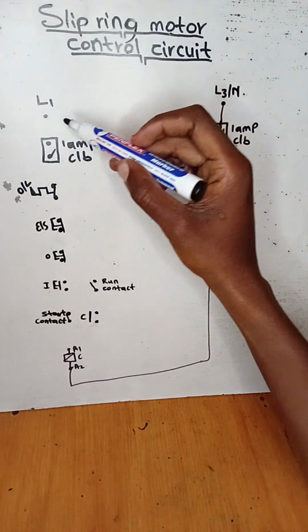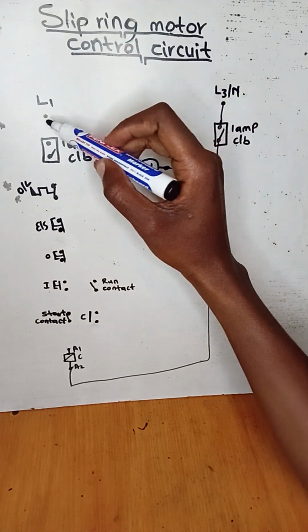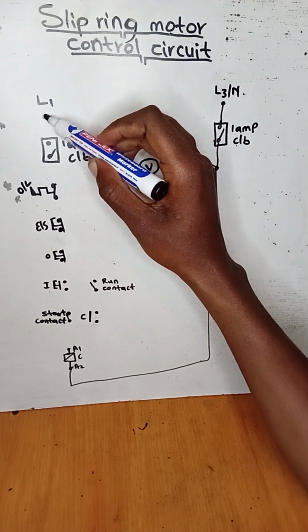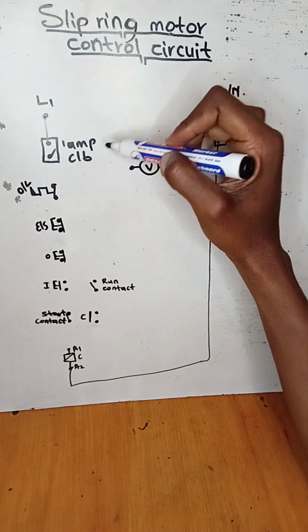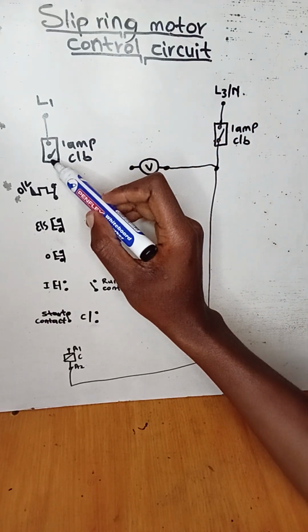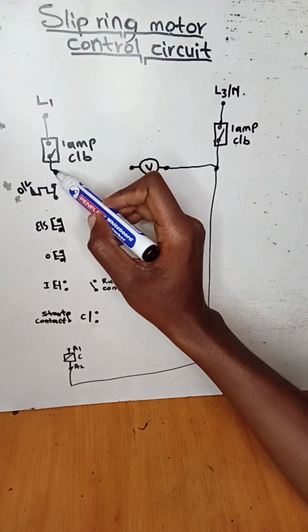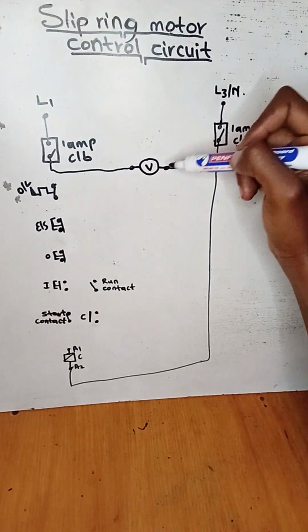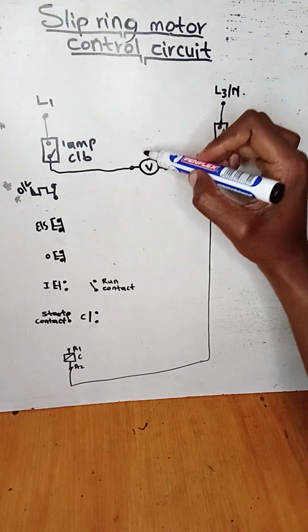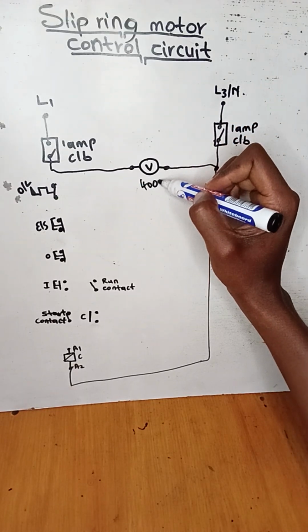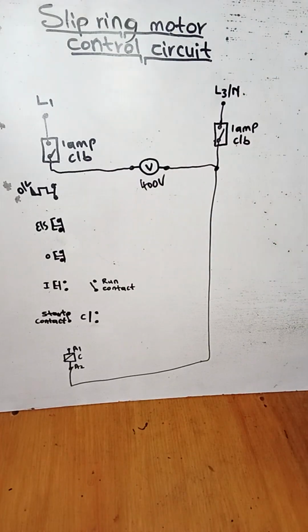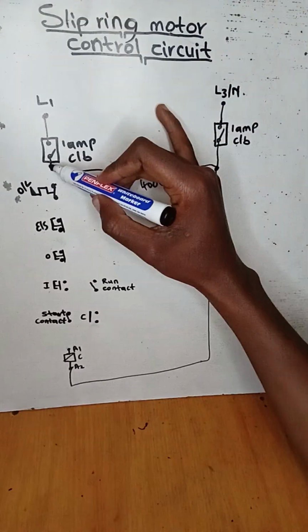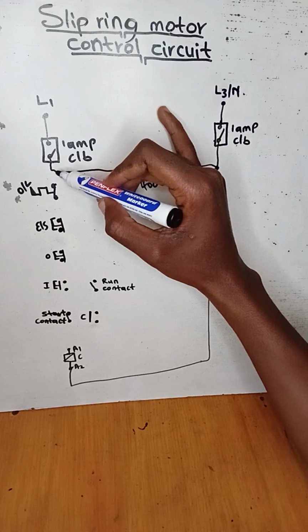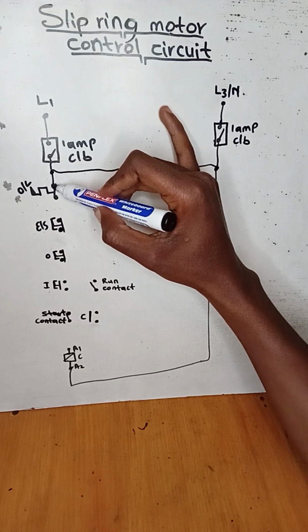So from the supply of live 1, it will be connected to the in point of the 1 amp circuit breaker, and the output of the 1 amp circuit breaker will be connected to the voltmeter, which will give a reading of 400 volts because we have connected it with a 3-phase supply. Right.